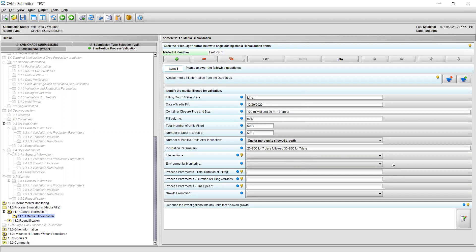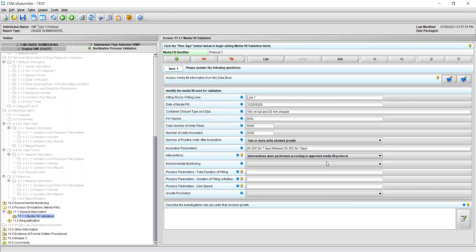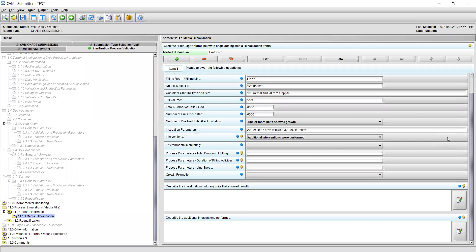In field 9, identify if interventions during the media fill are performed according to the approved media fill protocol by using the drop-down menu. You may select either interventions were performed according to the approved media fill protocol or additional interventions were performed. If additional interventions were performed, a new field will appear asking you to describe the additional interventions, why they were performed, and their potential impact on the media fill. If these interventions will be included in future media fills as routine interventions, an updated media fill protocol should be included in section 14.0 Evidence of Formal Written Procedures. Please note that a copy of the current media fill protocol should also be submitted in section 14.0.